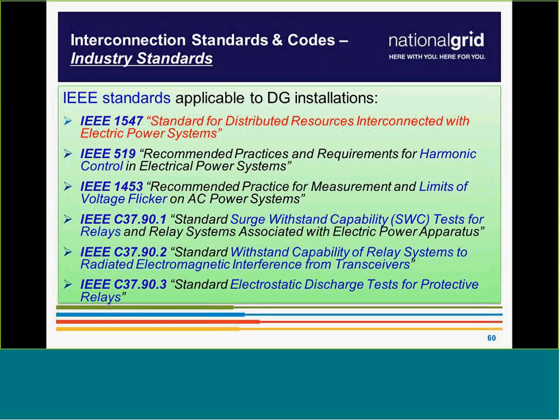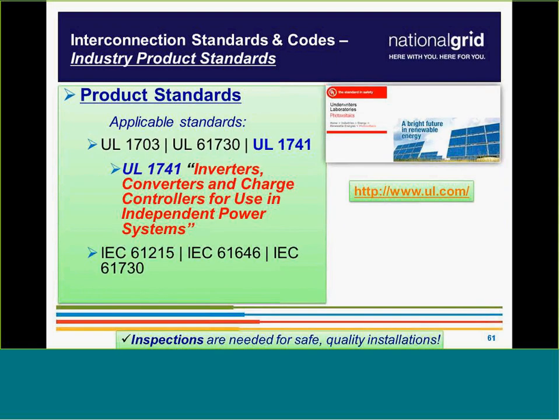We get a lot of frequent questions about what we mean by utility grade. Really, we want to make sure you're meeting the requirements in IEEE 1547, to make sure that relay has the surge and transient withstand requirements of the C37.90 series - basically to make sure it's built as if we build our own equipment, so it can withstand what it will see when connected to the power system.